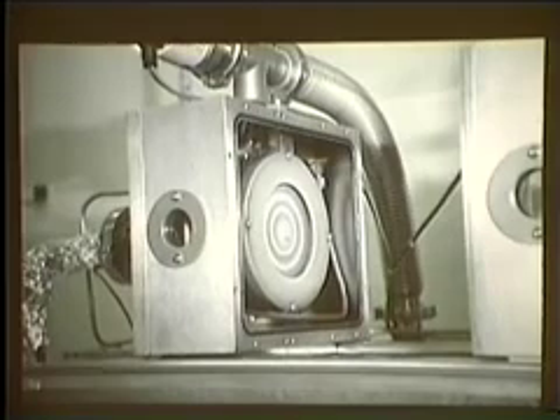Our tritium scrubber is a design modeled after the tritium scrubber in use at Lawrence Livermore. A tritium scrubber positioned after the two vacuum pumps is used to strip tritium from the chamber effluent by converting the tritium gas into tritiated water, which is collected in a desiccant. The scrubber consists of a stainless steel cracking chamber filled with catalyst, which is heated to a temperature of 1,000 degrees Fahrenheit to ensure combustion of hydrocarbons over the catalyst, including methane. The heat is provided by a tube furnace, which maintains constant temperature to within 2 degrees.